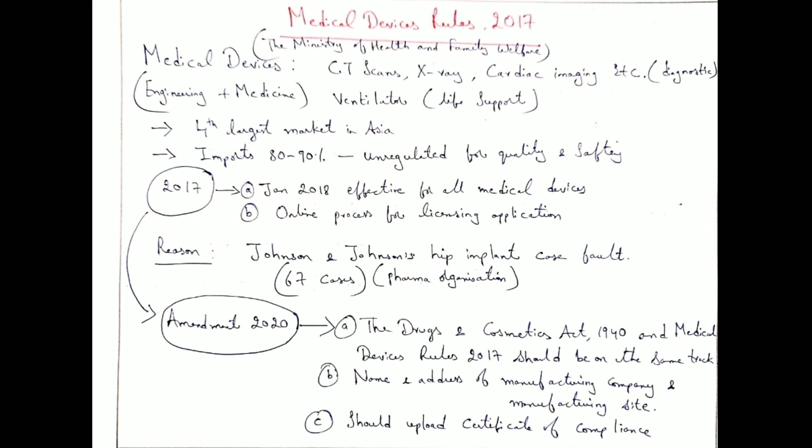The Medical Devices Rules 2017 saw amendments in 2020. These rules fall under the Drugs and Cosmetics Act, 1940, and the 2017 rules have provisions outlined under this framework.